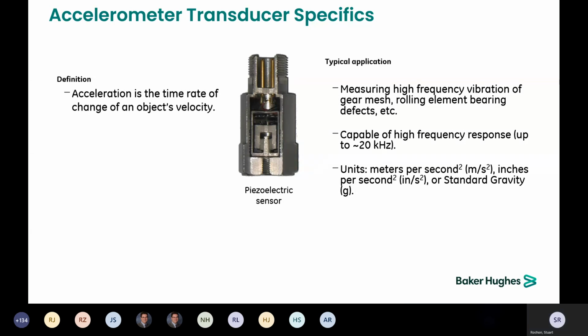So for something like an earthquake sensor, having a large mass where there is a lot of energy moving very slowly makes sense. Having a small mass at high frequency makes sense. So making sure that you're using the right size inertia mass to get the appropriate frequency range that you need to monitor is important. And they generally output in inches per second squared or Gs.